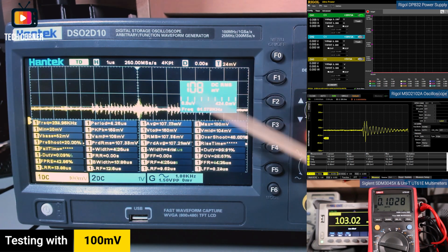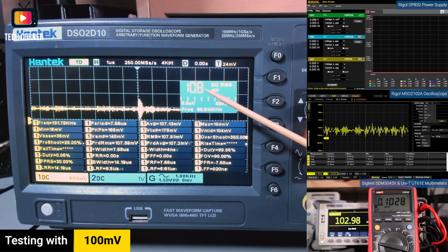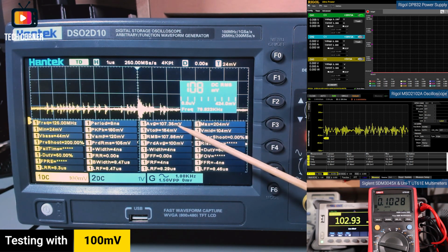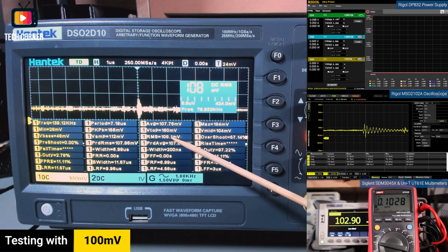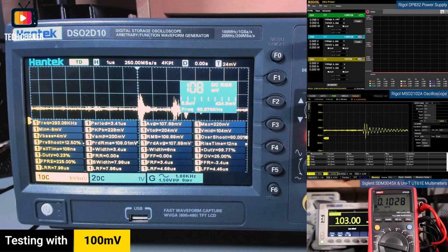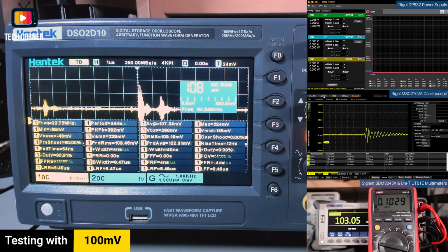In terms of the Hantek, it says 108. It still has that 5 millivolts difference. 107 on average and 107 on RMS. Let me just do an auto set on the Rigol and see what values it gives us now. So we have 104.4. It's 1 to 2 millivolts over the voltage that we have on the multimeters. Yeah, I'm good with this.